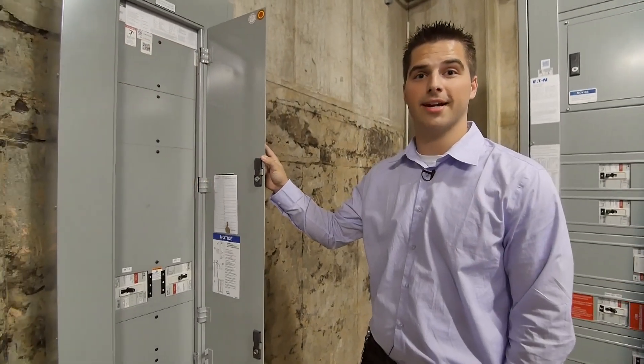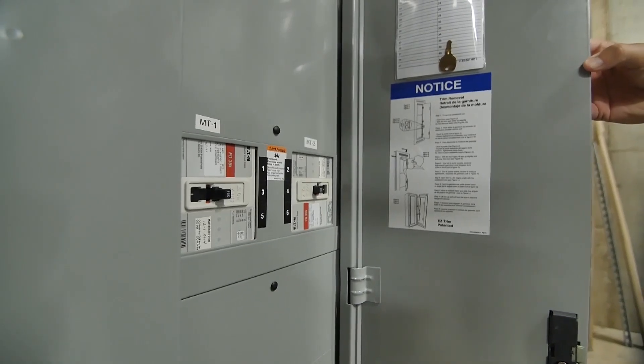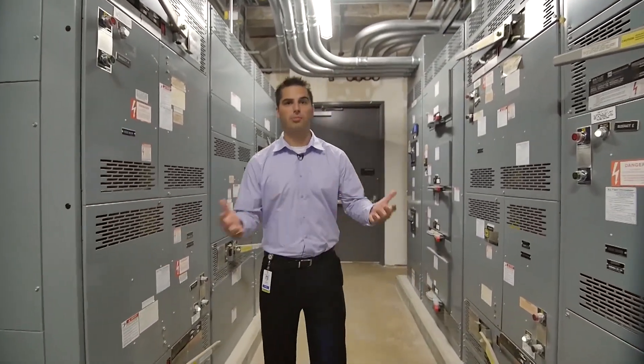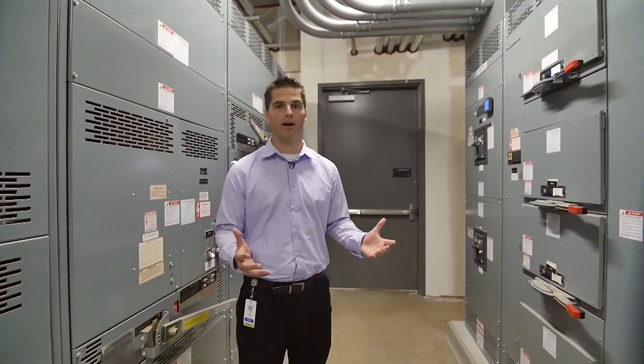This is the microturbine contactor panel. It has contacts that isolate it from the existing utility grid. The reason for doing this is that the microturbines need to ramp up system voltage and have the correct phase angle. This is switchgear 3 and this is switchgear 4. We also purchased additional CTs for each of these existing switchgear to have a better understanding of our overall system.